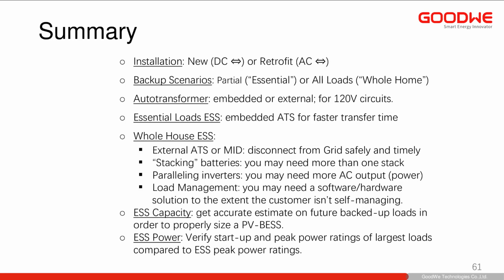Do you need load management? There are plenty of solutions out there if the customer isn't self-managing. Finally, ESS capacity really depends on doing proper load calculations, so look back at the slides to see how to do that. On the power side, be careful about inrush current loads, whether metering or checking the nameplate—you want to consider those, because the last thing you need is the grid going out, systems restarting, too much inrush current, and no backup power.